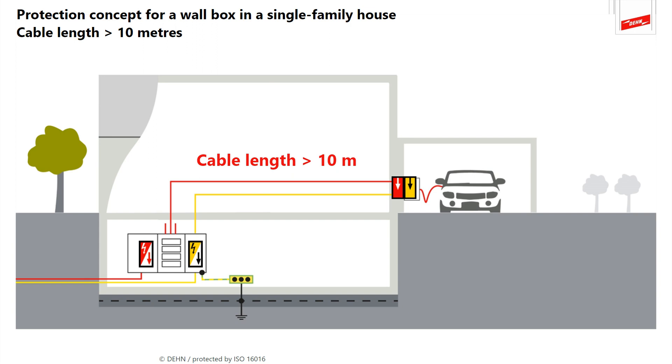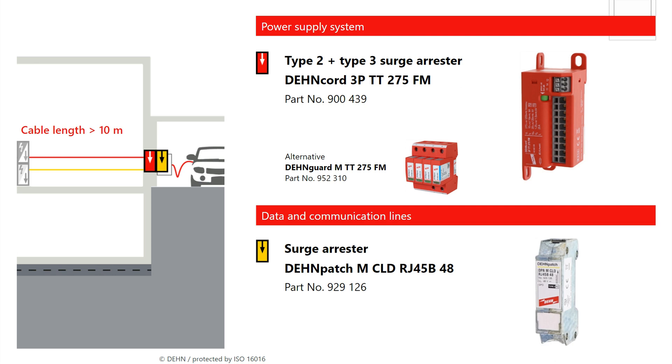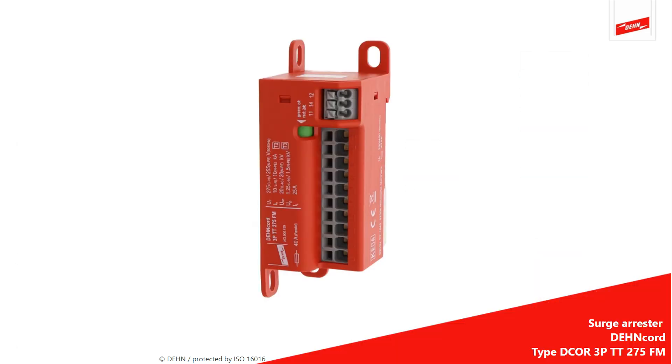The 10-meter rule also applies to data and communication lines. Protect the power supply of the wall box with DEHNcord 3P, a compact type 2 and type 3 surge arrester. This arrester meets the normative requirements and reliably protects the wall box and electric vehicle. Why DEHNcord 3P? With a width of only two standard DIN modules, this surge arrester fits into almost any installation space, making it ideal for use in wall boxes.